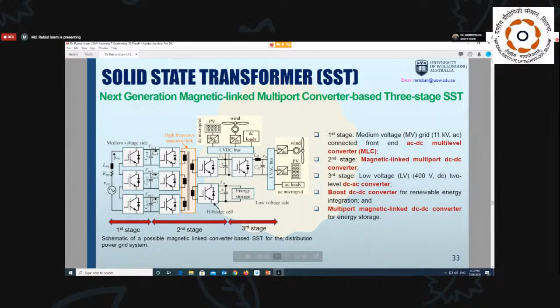So you already realized that the magnetic link is the main component in this medium voltage converter, multi-level converter, or solid state transformer. Therefore, it is a big challenge to design an optimal high frequency magnetic link, and also a challenge to find good magnetic materials which have high flux density and low core losses.